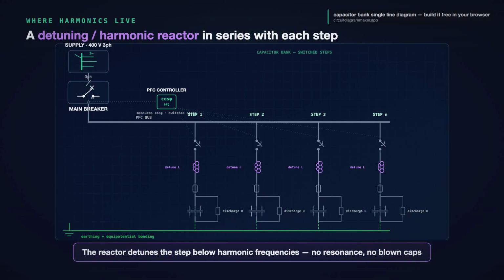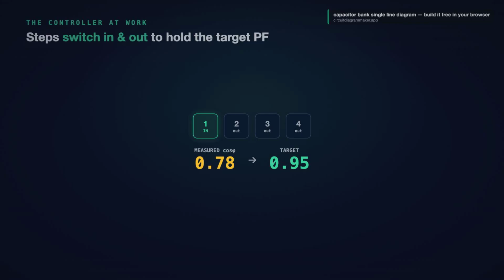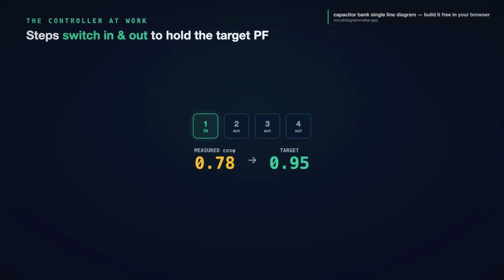It shifts the resonant point of that capacitor plus reactor branch below the lowest troublesome harmonic, commonly around the 5th, so the bank can never resonate on it. Where there are harmonics, that series reactor is not optional. On the one line, you show it in series, above the capacitors on every step. So watch the bank actually run.